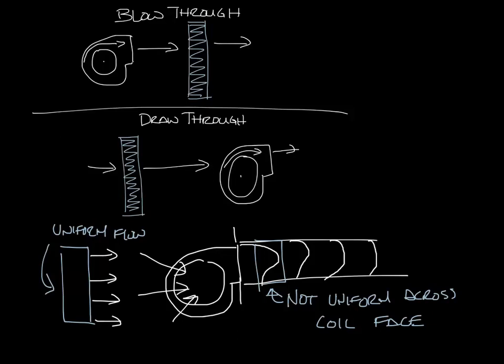If you use blow-through in these situations you may need to put the coil further away from the fan to allow for the air to become more uniform and then that'll add length to the unit which will add costs and take up more space. For this reason most air handlers are draw-through.